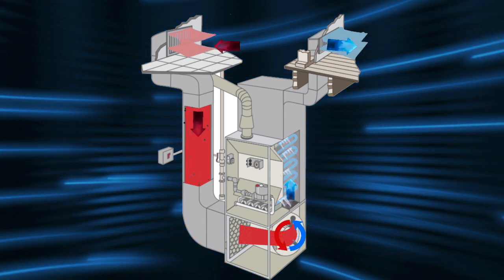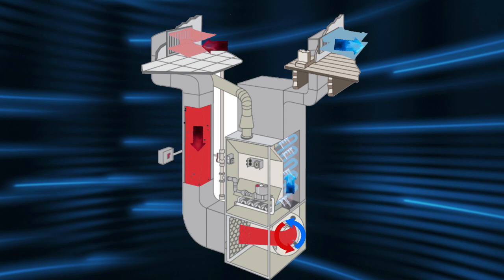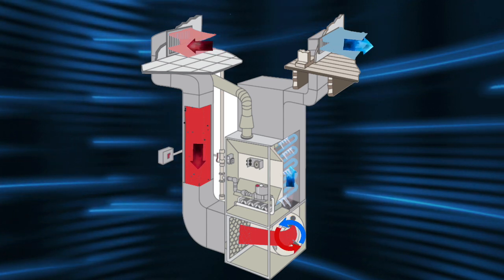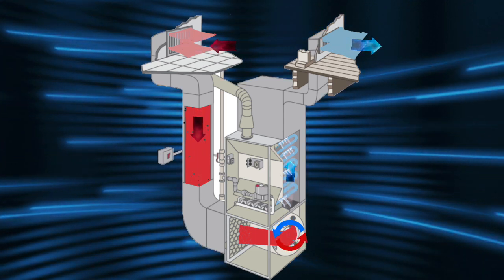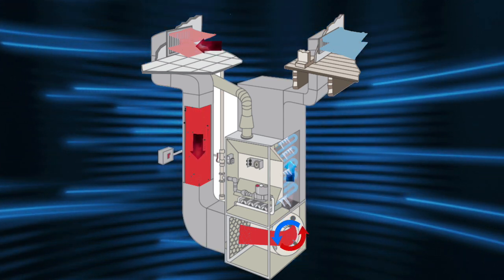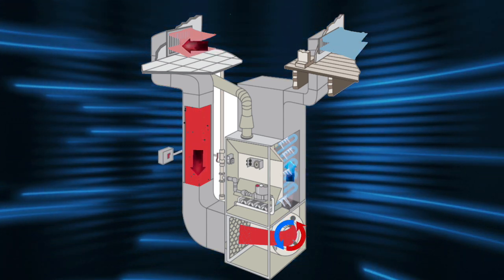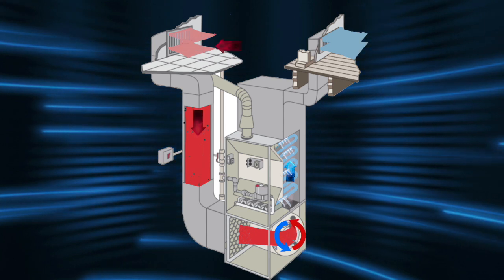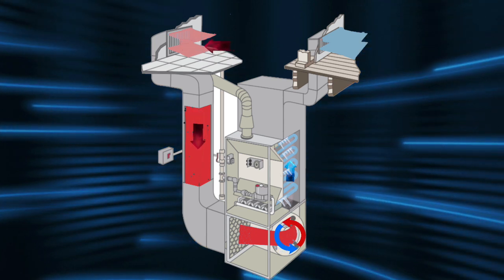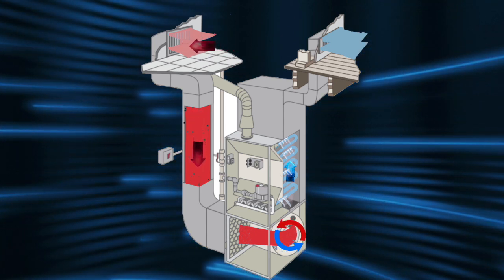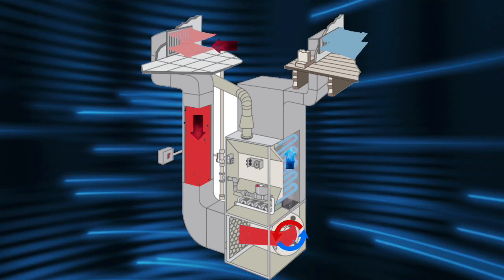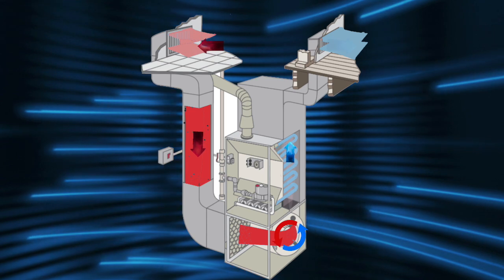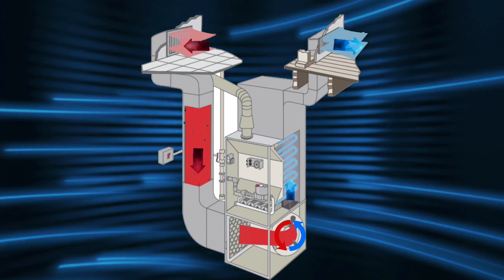When ice forms, air will eventually stop flowing through your coil. By always making sure to have 400 CFM of cooling per ton flowing through the coils, you can ensure proper coil temperature to allow water to condense and not freeze.